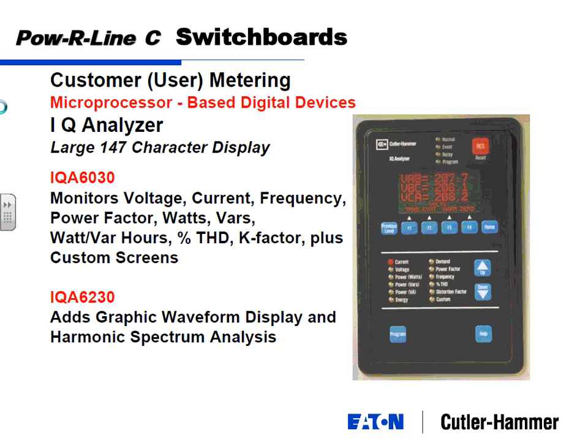Likewise, you can kick it up a notch into what I would call a power quality meter. There are energy meters and power quality meters. Power quality meters will give you all the energy information, the amps, the volts, the watts, the watt hours, etc. But they also give you information on power quality, things like harmonic distortion, things like K factor, or waveforms, graphic waveform display. So on the front of this unit, and this is an older one too, but nowadays on the front of a meter itself, you can actually look at a waveform, see what it looks like.